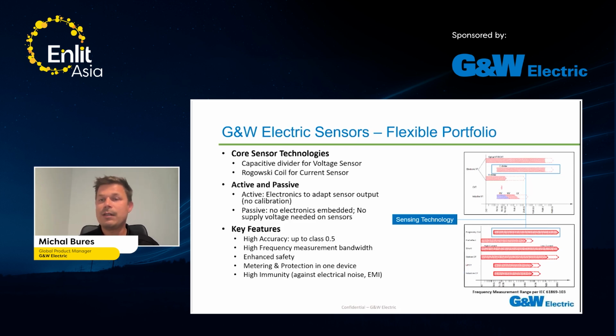Also, we are using active and passive sensors. This is one of the biggest differences between us and our competitors, that we are using both of these approaches. So we are, let's say, taking advantage of the benefits from both worlds. With the active, there is electronics inside, so you can adapt the sensor output. You don't need the calibration coefficient or whatever. And for the passive, there is no electronics inside. You don't need the supply voltage.